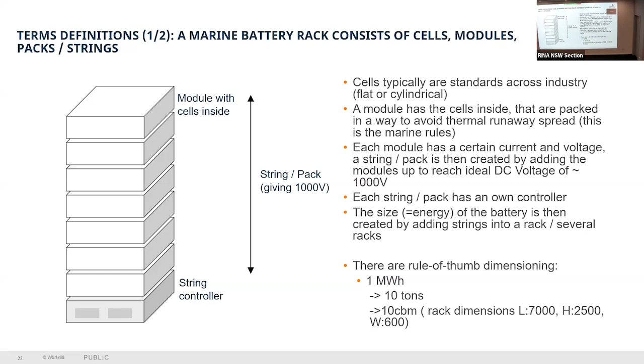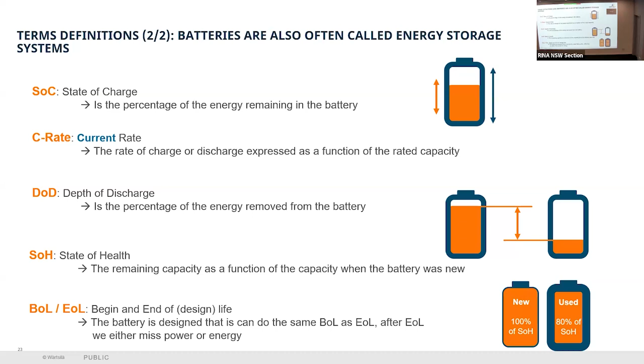So these are some definitions. Batteries are also often called energy storage system, ESS. These are some terminologies used when we talk about batteries. SOC is state of charge, the percentage of energy remaining in the battery. C rate, current rate, is the rate of charge or discharge expressed as a function of the rated capacity. DOD, depth of discharge, is the percentage of energy removed from the battery. State of health is the remaining capacity as a function of the capacity when the battery was new. BOL, EOL is beginning and end of life. The battery is designed so that it can deliver the same at BOL as at EOL; after EOL, we either miss power or energy.